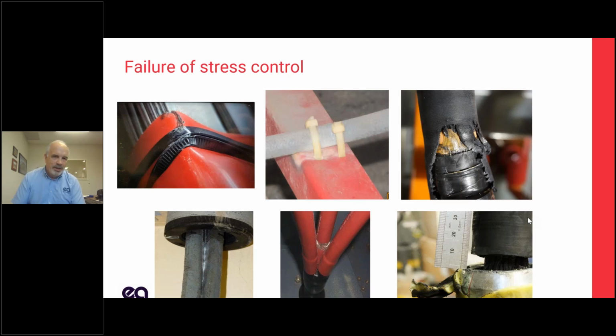You can see in the upper left, there's PD going right from the tie wrap to this bus bar. In the lower left, you've got two phases of unshielded cable. They're too close to one another. You see that white powder? That is the insulation actually starting to break down. The center bottom is where you've got a trifurcated cable, and at that crotch, the shields were cut back too low, and they're too close together. So where we go from the nice shielded portion to the unshielded portion is where things have gotten too close together, and we've got a lot of discharge. We've got that white powder. I'm sure we've got tracking inside, and a variety of other problems.